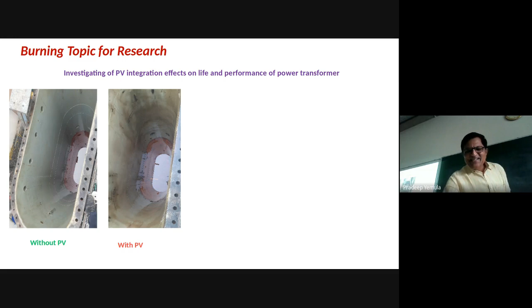If you see the core lamination, a transformer without PV is straight. Here it bends. This winding will fail if we leave it for another 2-3 years. Why has this happened? One reason is the power transfer is only one-way traffic, but here it is two-way traffic. When solar is there, power is going and coming back. These transformers are not designed for that.